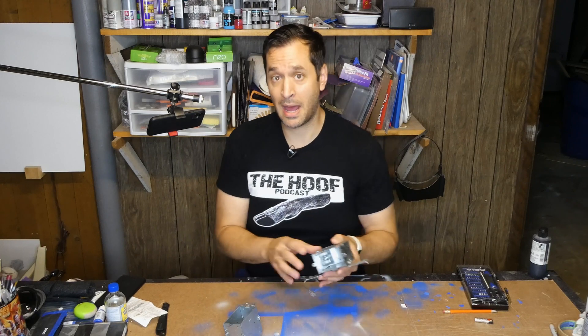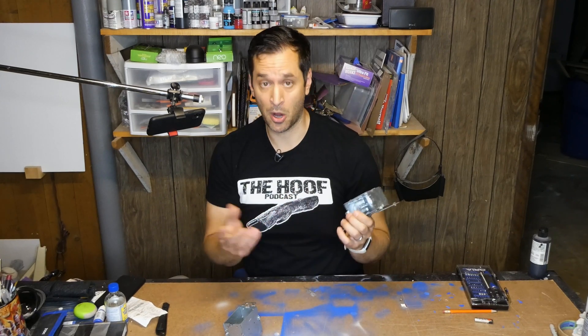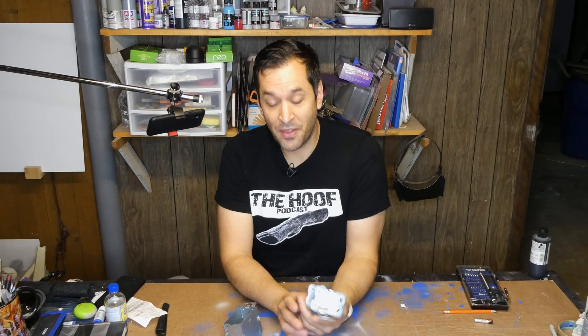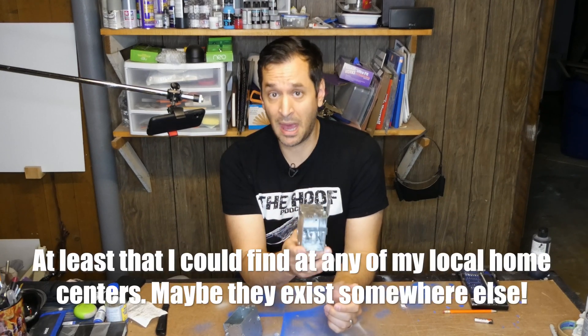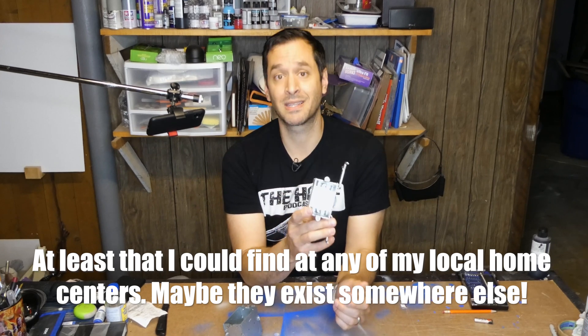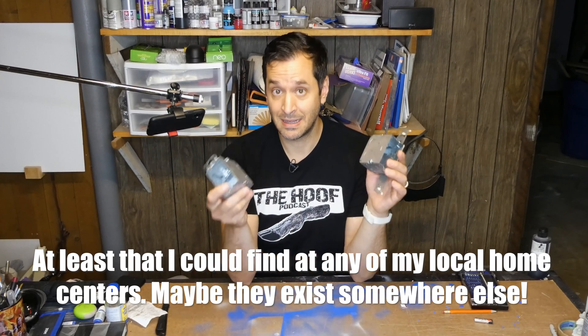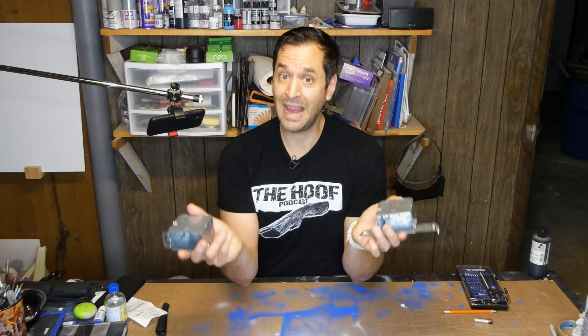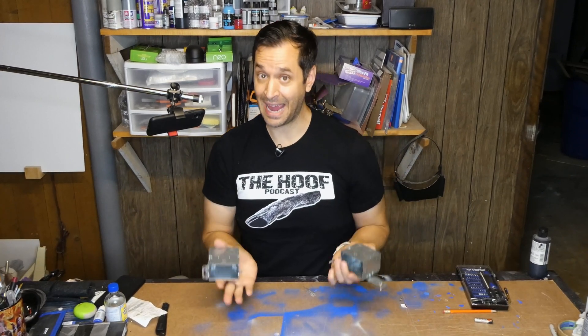And because that's metal armored cable, I have to use a metal box — I can't use a plastic box. Now, they don't make double gang metal boxes, but they do make single gang boxes, and some of them are called gangable — yes, gangable.